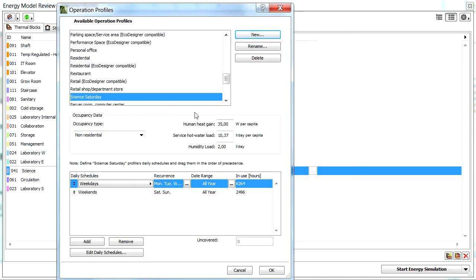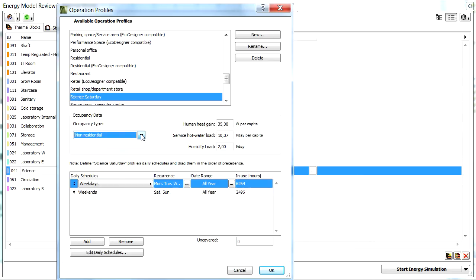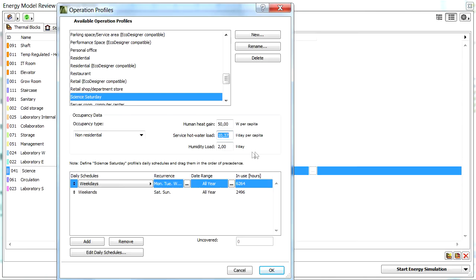Let's make sure that the Occupancy Data Type is non-residential. We will enter 50 watts per capita for human heat gain, 20 liters per day per capita value for the service hot water load, and finally, 4 liters per day value for the humidity load.